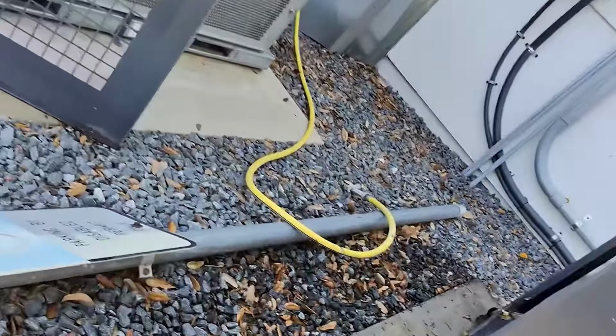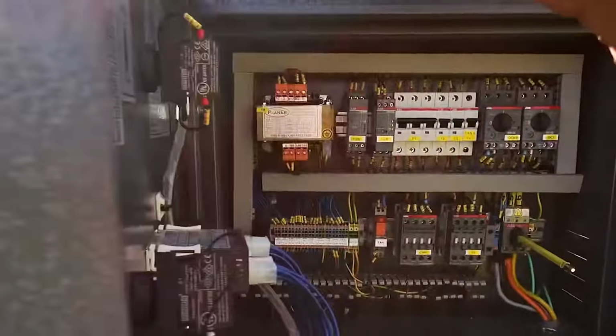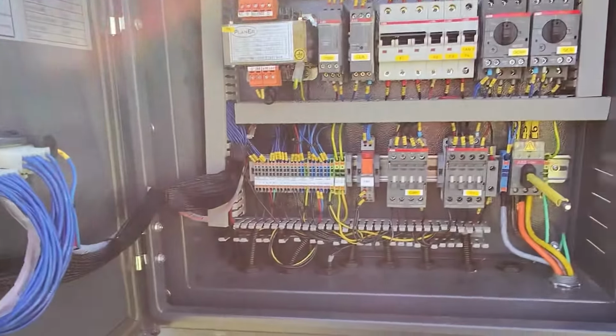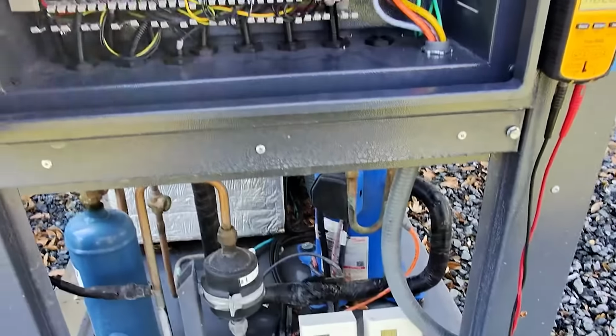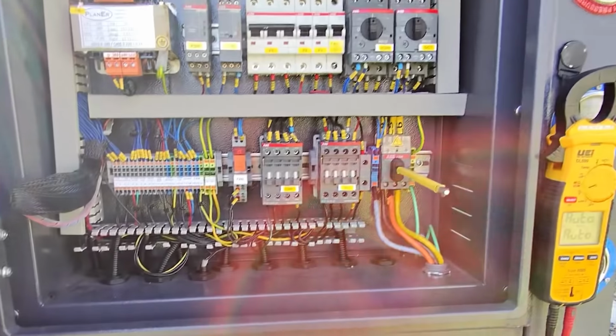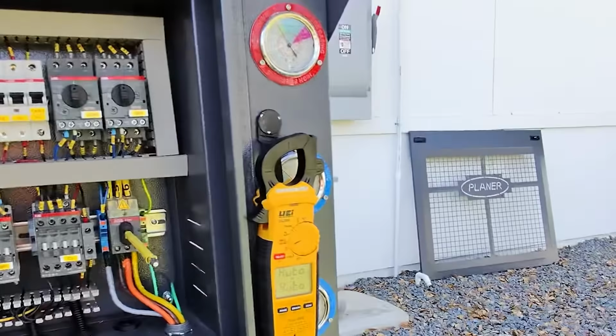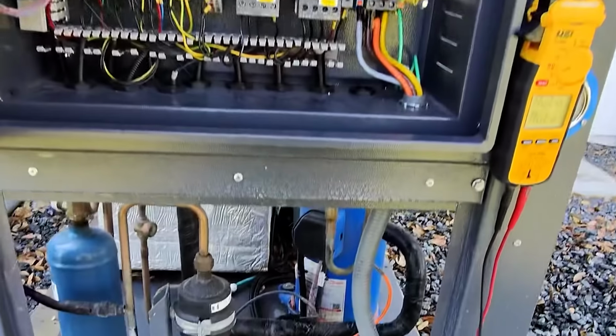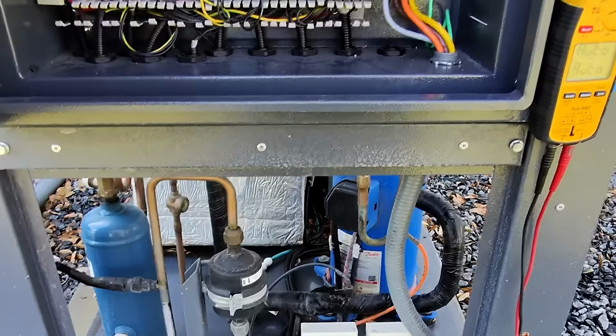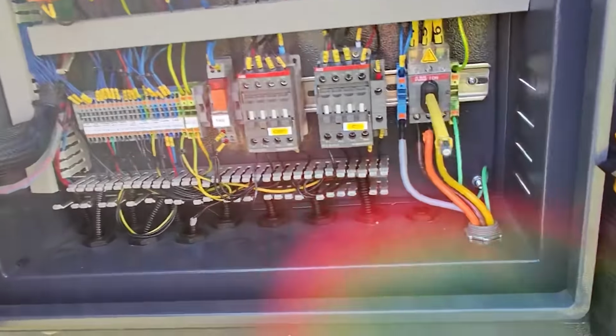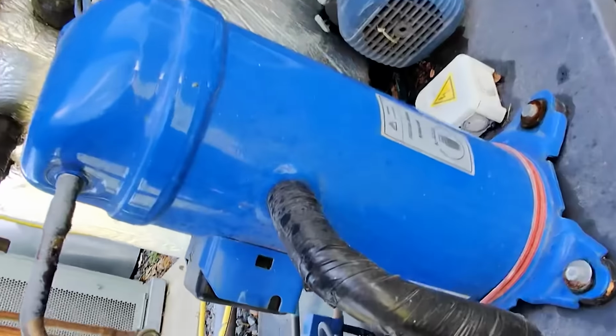Now, I did clean the outdoor coil, right? It's always a good idea when you get a high pressure trip to just go ahead and wash the coil. There's nothing worse than finding out, well, you know, the fan runs, and it was running when I got here. It wasn't running anymore, but it just means that now I've got a clean coil and I've got a fan running. So one less thing for me to have to check the box on.